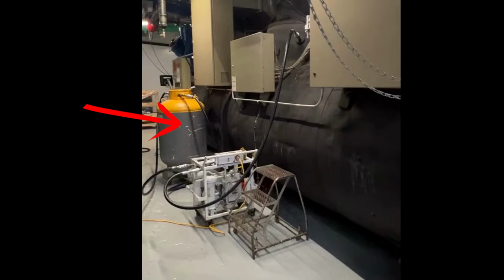Now keep in mind, make sure you are flowing water through the tubes when you're doing this process. With push-pull, freezing tubes is less of a concern. And I do say less, not no concern. It is less of a concern because technically we're not dropping the pressure on the chiller, so our liquid refrigerant should not get below a freezing temperature. Should is the key word I want you to hold on to here.